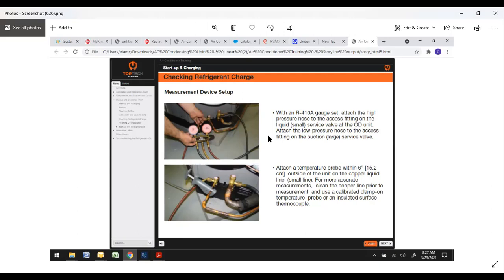A lot of guys I see, in fact most I see, are using some sort of digital gauges, whether it be like the S-Man or Fieldpiece, or a lot of guys are going to the Bluetooth now, where everything's Bluetooth and all you have is your probes clamping on. All those will give you the superheat and subcooling. It's basically all built in to the program for you. So that takes all the guesswork out of it. Years ago, we had to carry a probe similar to what you see in this picture here, and then hook it to my meter and turn it on temperature and compare that temperature to my gauge, which is fine. It's not rocket science. But with those new digital gauges, whether you're using an app or like an S-Man, it tells you exactly on the screen what your superheat and subcooling is. They take all the guesswork out of it for you.